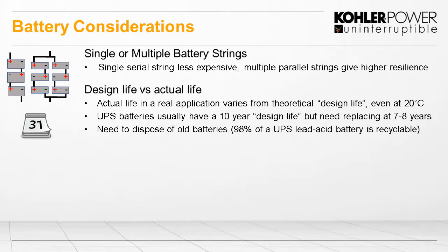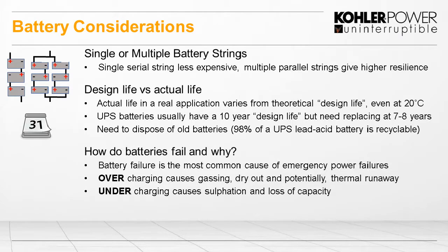All design lives are typically around 20 degrees. Now, in reality, that might not always be 20 degrees. But a typical UPS battery with a 10-year design life would need replacing at 7 to 8 years. And once disposed of, they are recycled and should be recycled. And the good thing is 90% of the actual battery can be recycled. But so why do they fail at 7 to 8 years rather than the 10-year design life?